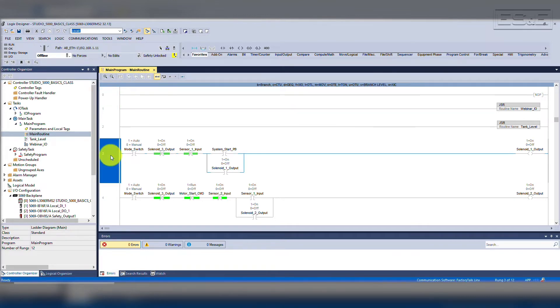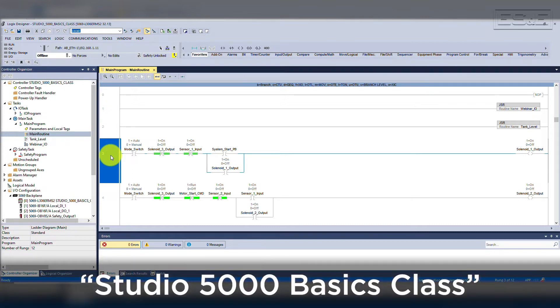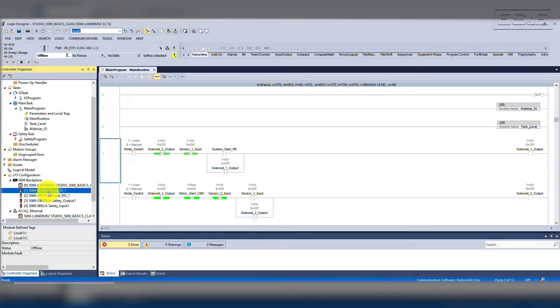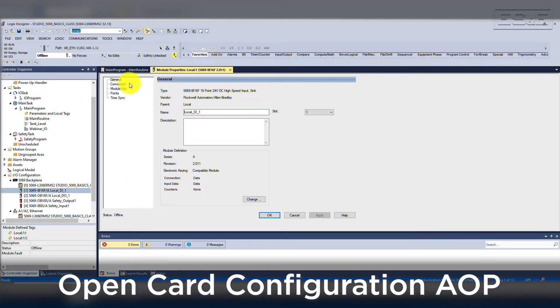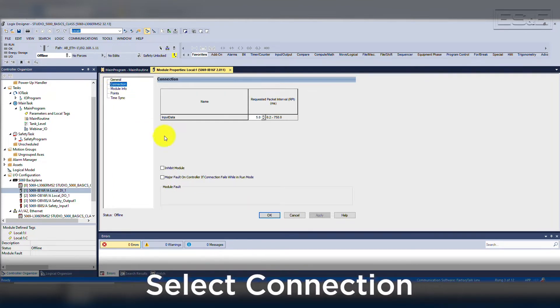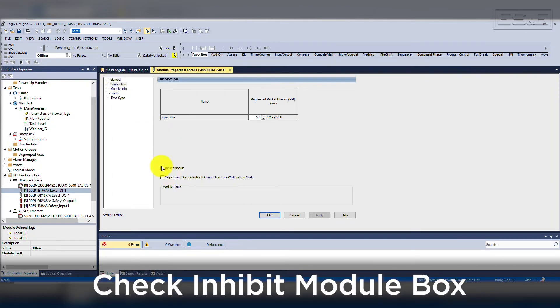Let's open Studio 5000 Logic Designer. I have a project already created that we will be working with. The program name is Studio 5000 Basics Class, which has a 5069-L306ERMS2 controller set up for DLR. You can see a few local I/O cards that exist in the controller configuration. Since we are not going to utilize the I/O, we can open the card configuration AOP, select Connection, and select the checkbox for Inhibit.